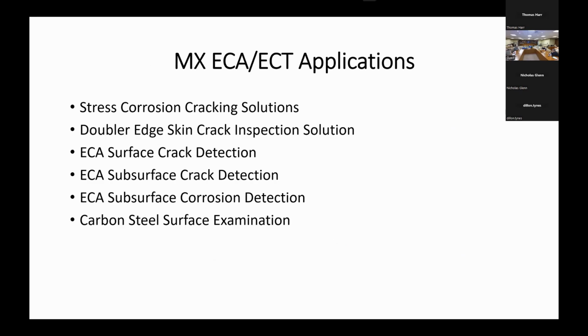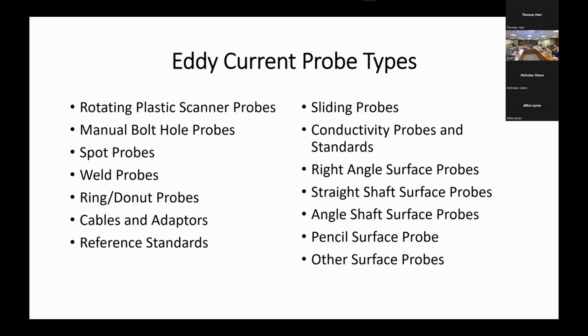So, some applications where the MX ECA is used: looking for stress corrosion cracking, doubler edge skin crack inspection in the aerospace industry, surface and subsurface crack detection, subsurface corrosion detection, carbon steel surface examination. These are all examples of different applications where the ECA is used. And then we have a list of different eddy current probe types, whether they're for the Nortec 600 or for the MX ECA. Things like rotating scanner probes, manual bolt hole probes, spot probes, pencil probes, surface probes, whether right angle or straight shaft, conductivity probes and standards. We do offer several reference standards as well.